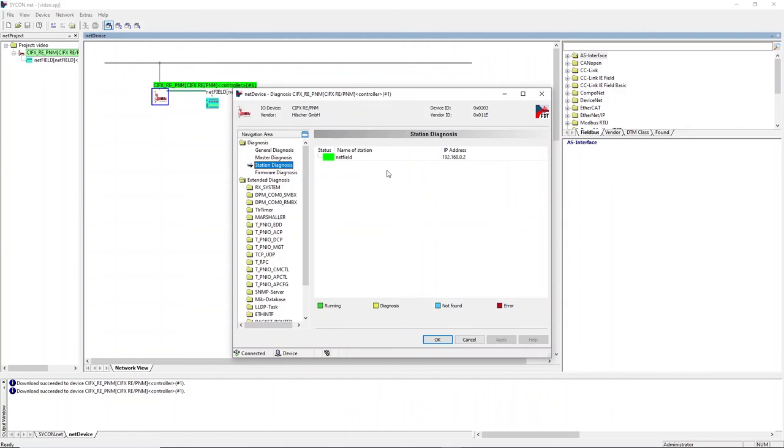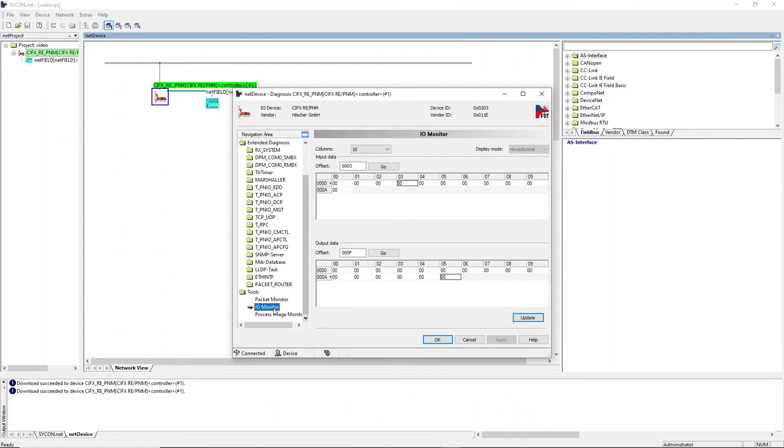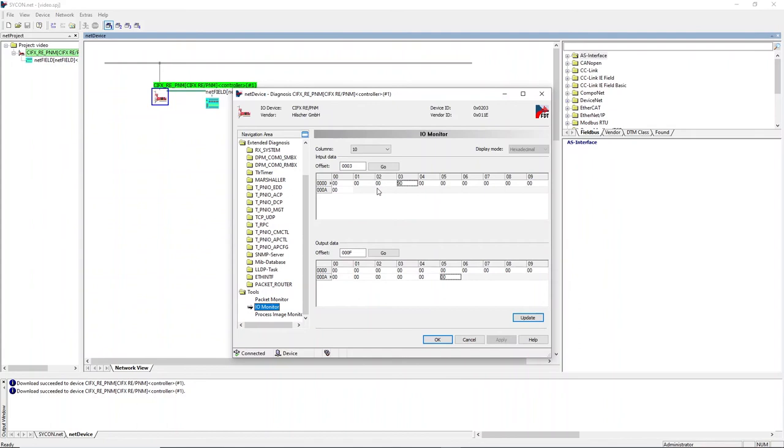To check whether cyclic process data can be transferred, open the IO monitor. The IFM display shows different values when pressing any button. This is visible here in the data input area. Also output data can be sent without any issue.